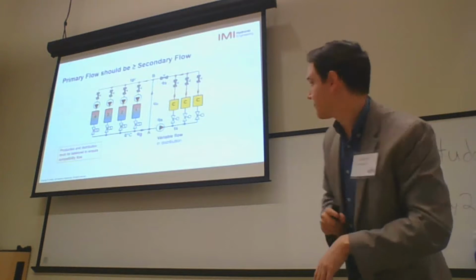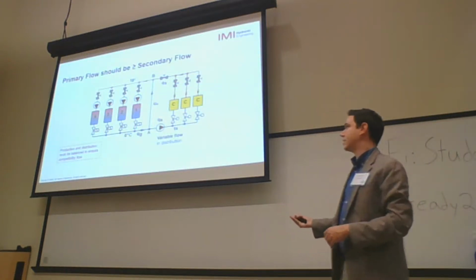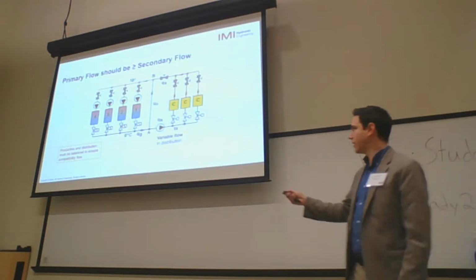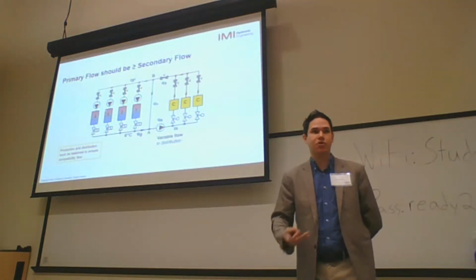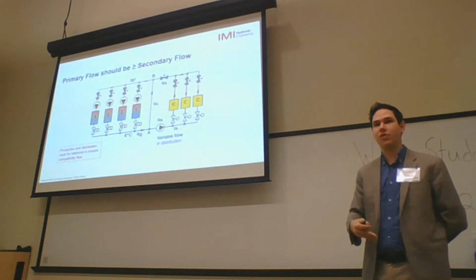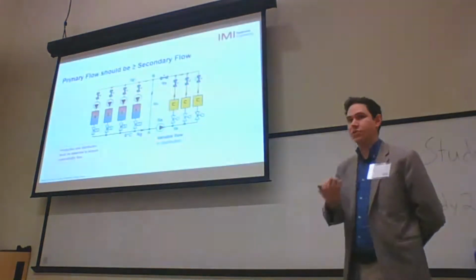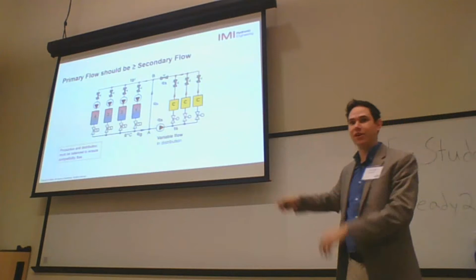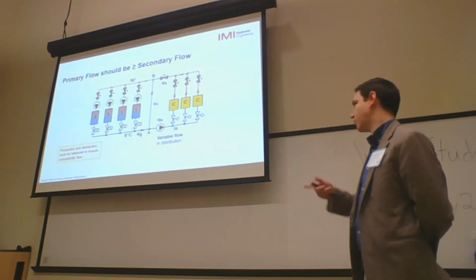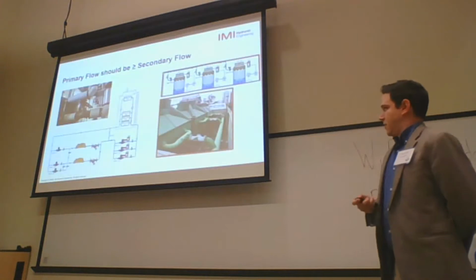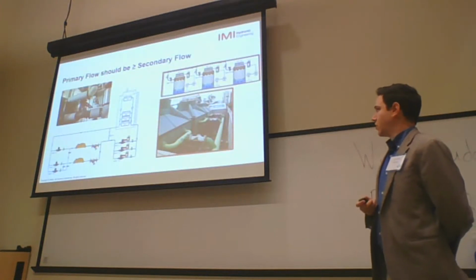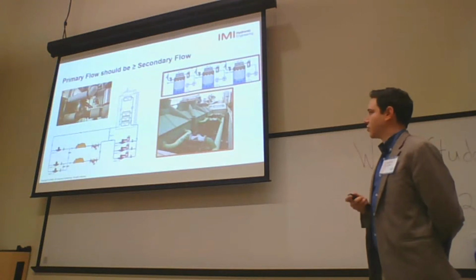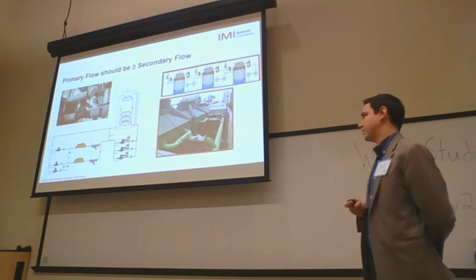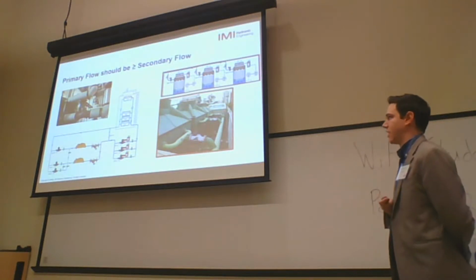Getting closer to the end of the presentation, primary flow should be equal or higher than secondary flow. Normally, on the primary side, we always have the right flow. Equipment manufacturers of chillers or boilers will not start up the system if they don't have the right flow rate. So the biggest challenge is always balancing the secondary side, where I'm assuming most of you spend much more time, more challenging, with more equipment as well. This is just an example of a balancing valve installed on chillers or cooling towers, making sure that you also have the right flow rate, equal or higher on primary than secondary side.